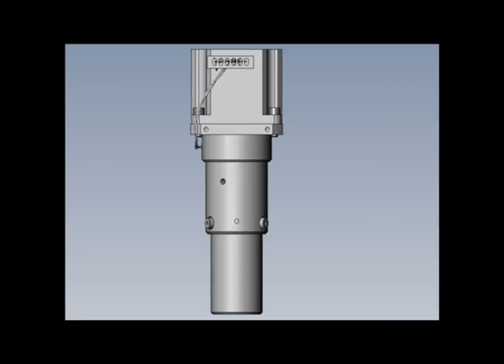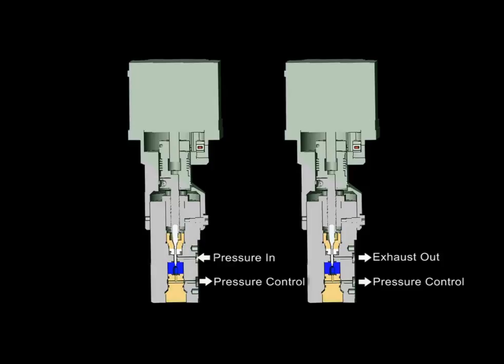Number three: the CPC-8000 contains a patented proprietary needle valve regulator that is designed to deliver the control pressure in a quick, reliable, and stable manner. A control stability of greater than or equal to 0.002% of full-scale is achieved.